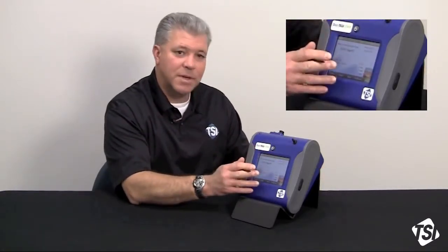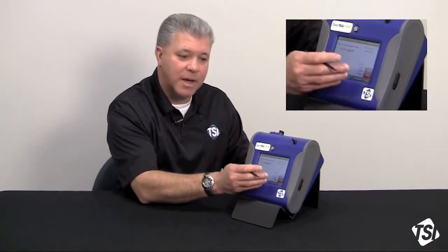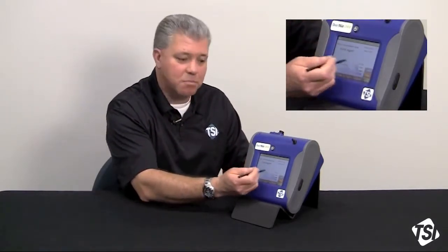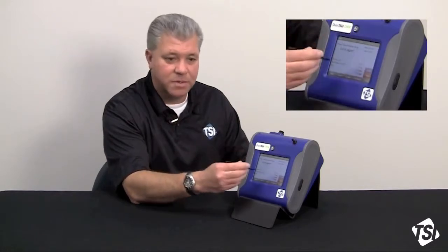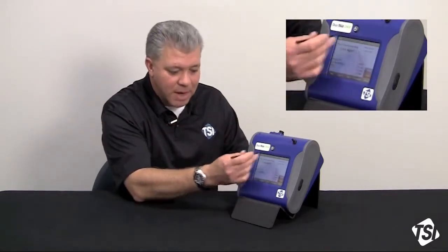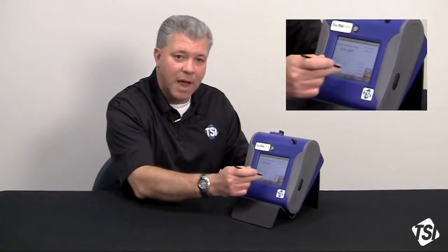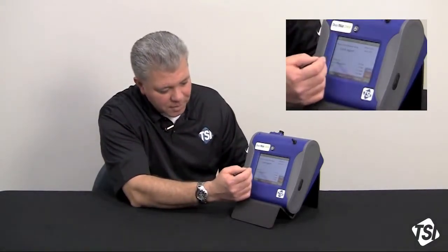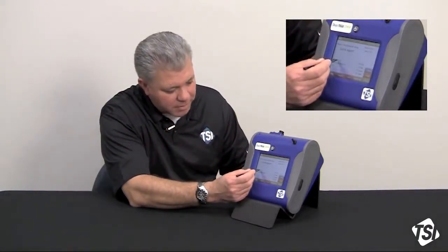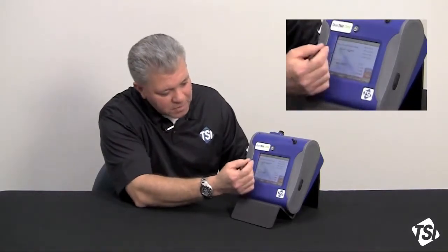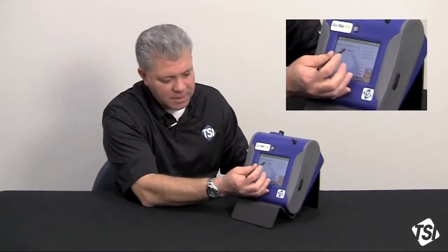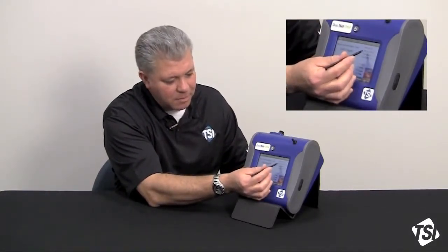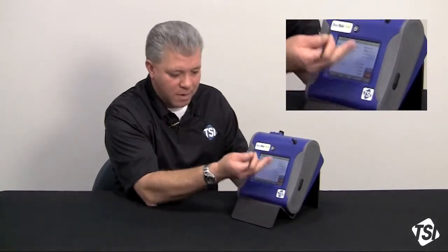Now, I want everybody to understand that if you are taking data, if you're logging data, and you start to switch these modes around, you will still log all channels. It's just what's displayed on the screen, on the smart screen, through the graphical user interface, and what we call these smart keys or live keys that are on the screen. So let's go back to all being displayed. Now we have all size fractions. I'm going to go back to total being the one that's highlighted, and then PM10, respirable, 2.5, and PM1 realign themselves.